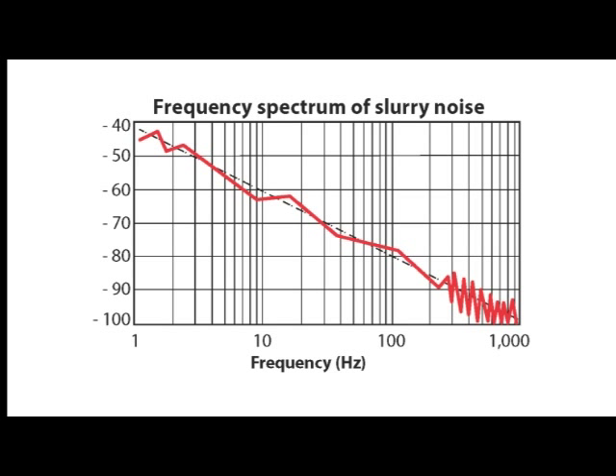Slurry noise has its highest amplitude on the flow noise spectrum at low frequencies. On the scale, you can see that as the excitation frequency increases, the noise level decreases. Signal sampling is synchronized with the excitation frequency. Conventional meters utilizing only low frequency DC excitation will experience the effects of slurry noise much more prominently as the sampling rate is very low. High frequency AC meters do a good job of reducing slurry noise — the higher the frequency, the higher the sampling rate, which lowers the effects of the noise generated. Typical AC magnetic flow meters run at 50 to 60 hertz, thus pushing it out to the high end of the noise spectrum and generating a cleaner signal.